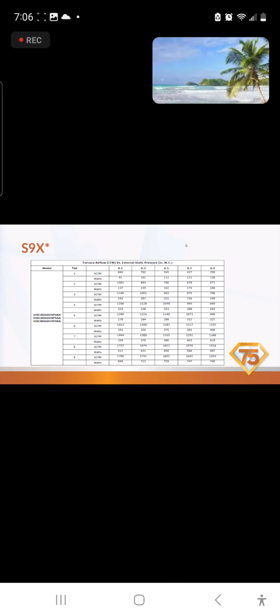When you are setting your speed taps, this is on the S9X models. Like I said, you have 9 speed taps. Your actual CFM will be completely dependent on what your static pressure is. You must take a static pressure reading once you have it running at your speed tap. That's why I would recommend you first see what your speed tap is set for, turn it on at that speed tap, and then check your static pressure. That way you know where you're at.